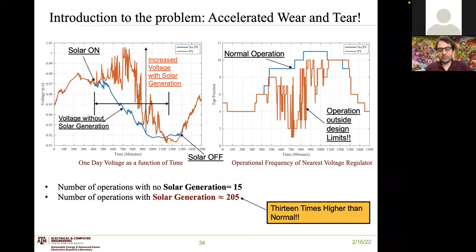When we have a highly variable voltage, it forces the regulator to operate outside its design limits. In this particular case, the tap changer is registering 13 times more operations than what it was designed for.